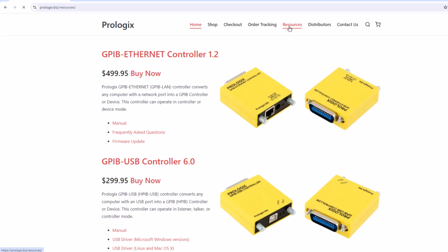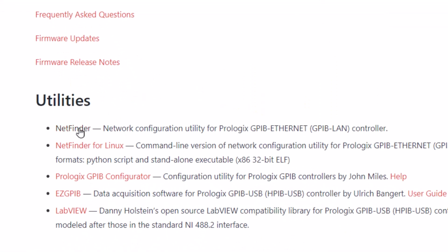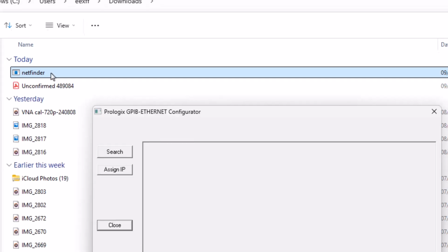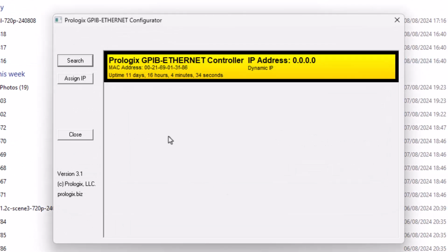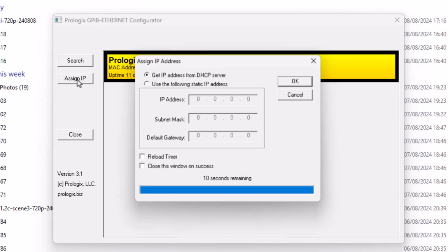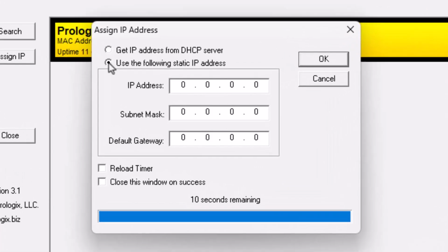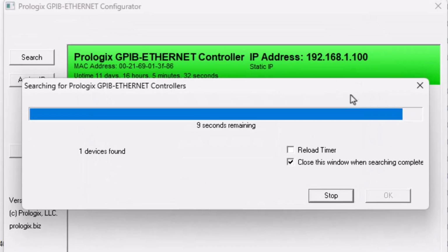Under Resources on the ProLogix website, click on NetFinder. Then run the executable file. Click on Search and the controller should appear on the list. Click on Assign IP and set a static IP address. Here I have chosen 192.168.1.100.